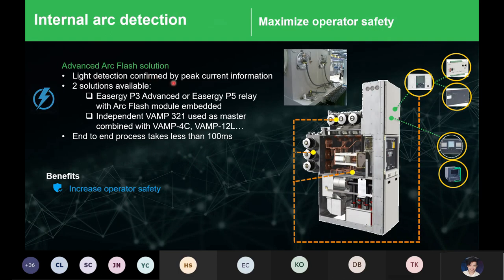Apart from this, we also have the arc flash solution that's installed using our Easergy P3 or P5 relay, which is embedded into the module. Just now we talked about the potential of arc flash, which is a concern in the switch gear. So we also have the independent VAMP 321, used as a master that combines with the different VAMP series. All these are our arc flash products that are available in our switch gear.